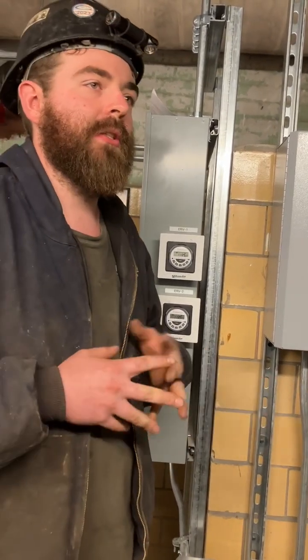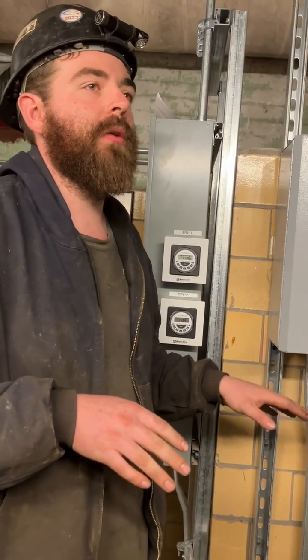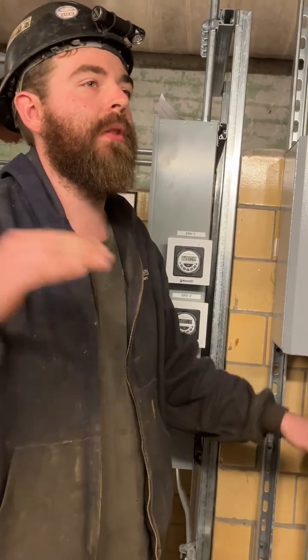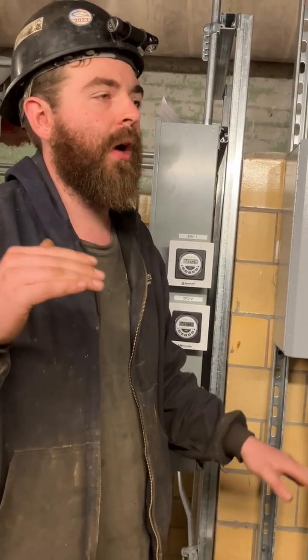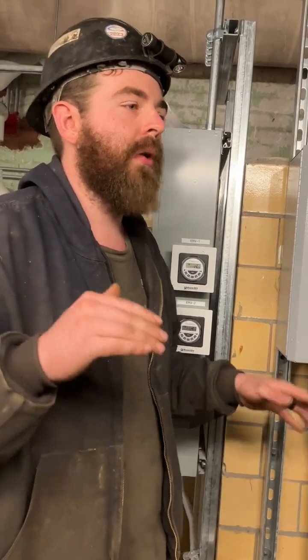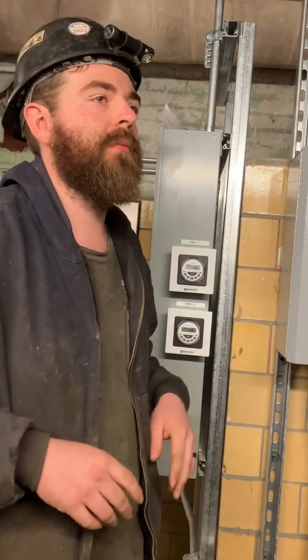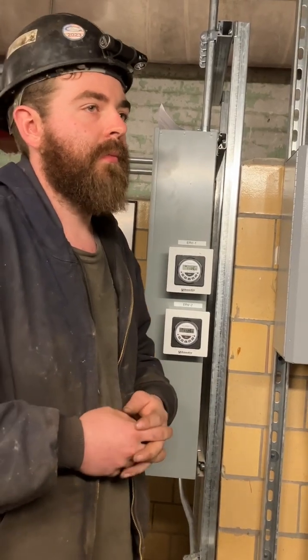It's a simultaneous system, so you can run heating in some parts of the building and cooling in some parts of the building. There's a huge delay for it to get into that mode from straight heating and cooling, for obvious reasons, there's a lot of logic going on there. But it does do that. It's not a heat pump system, it's a simultaneous system.